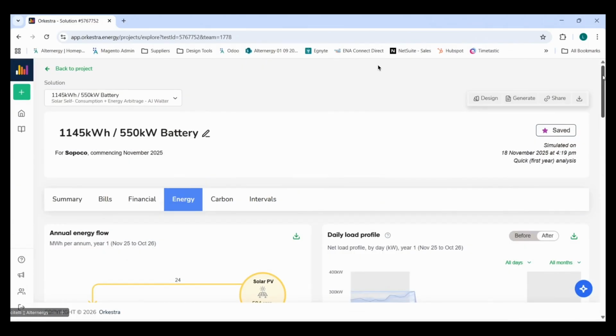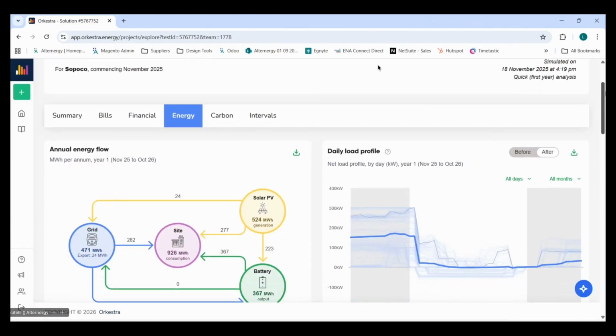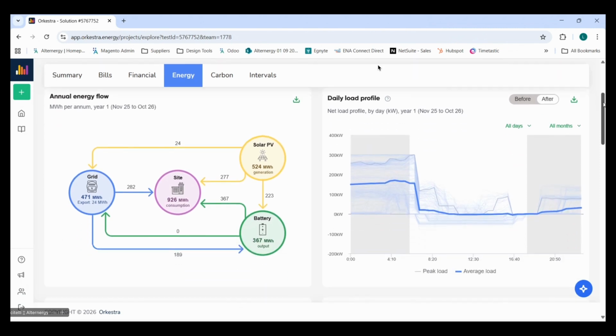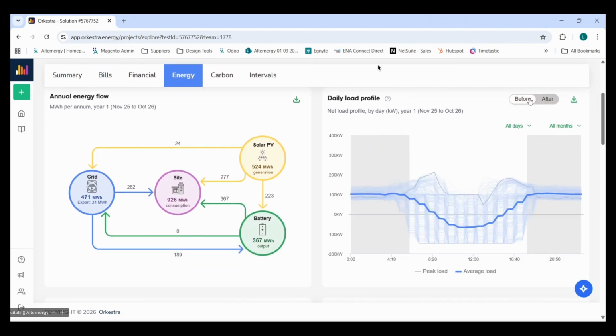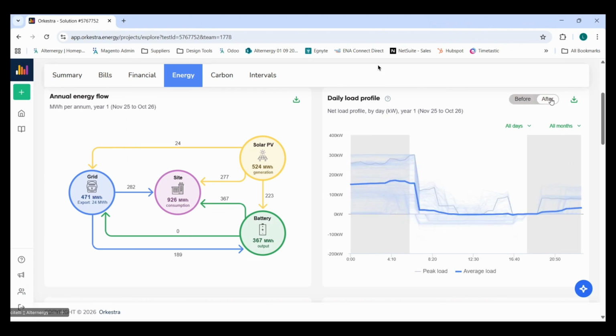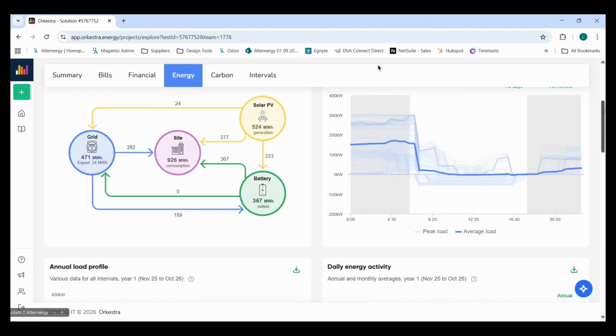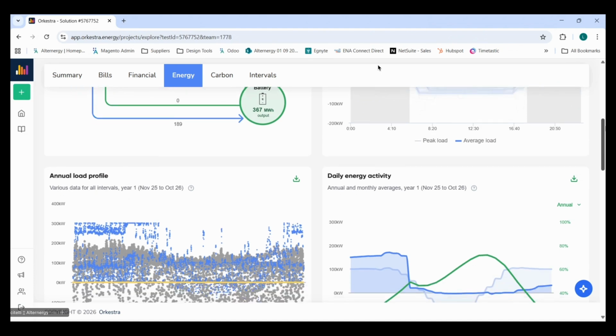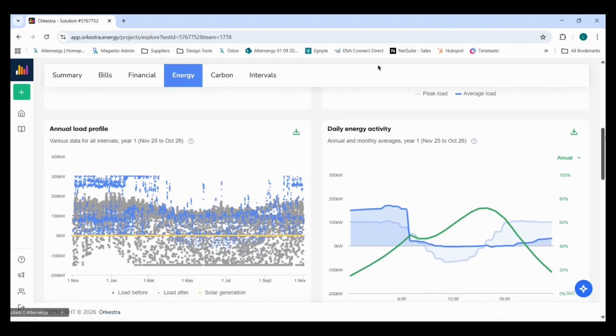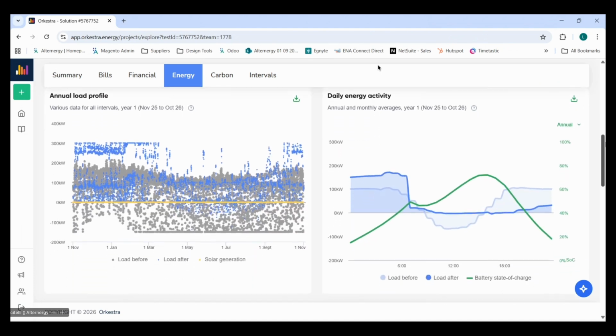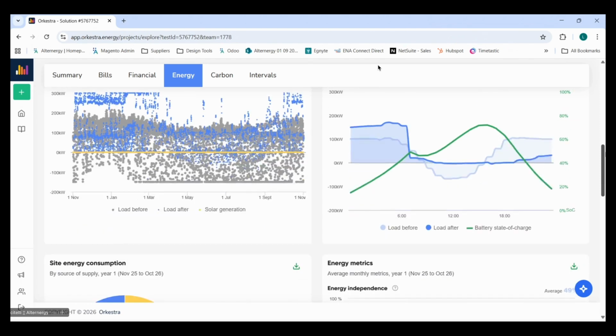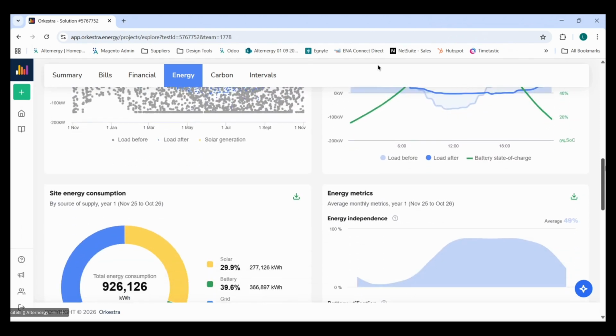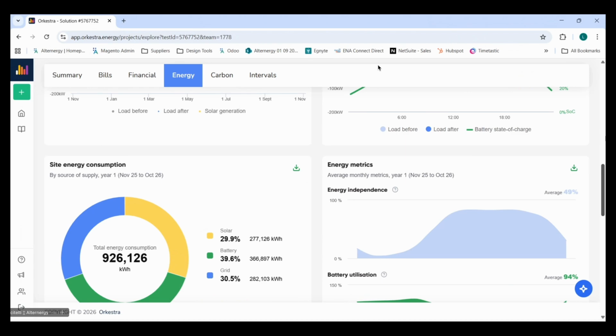From the initial approach, Sopoco provided half-hourly consumption data, the on-site PV generation data, and energy tariffs. The information was put into Orkestra, a financial modelling platform that helps provide optimal battery sizing. Orkestra generated performance results based on a range of 1 to 10 batteries, which identified 1.1 megawatt hours, or 5 229 kilowatt hour batteries, as a sweet spot for capacity, capital expenditure, and return on investment.